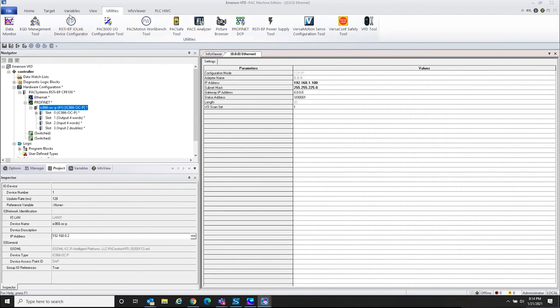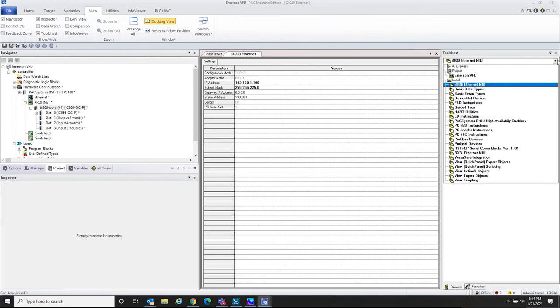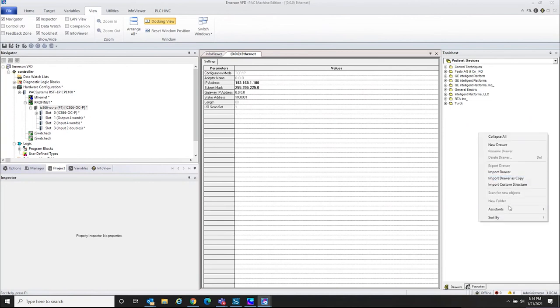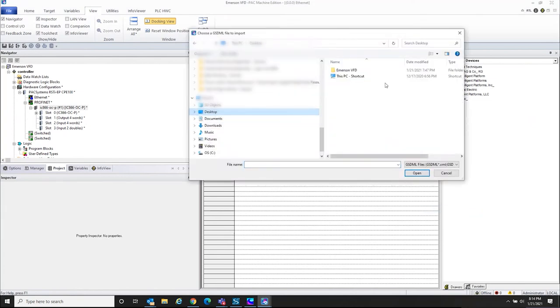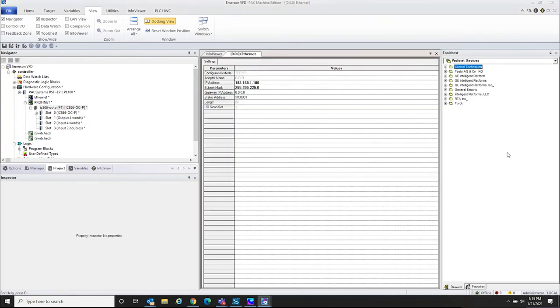I mentioned I'd show how to import the GSDML file. Going to the Views tab, I'll open the Tool Chest. There are many drawers in the environment — we'll concentrate on Profinet Devices. Here are the Profinet settings we were selecting from. To add another GSDML file to the tool chest, right-click in this area, go to Assistants, then Import GSDML File. We locate our file on the desktop, double-click it, and it automatically shows up in the Profinet drawer for use in any project.